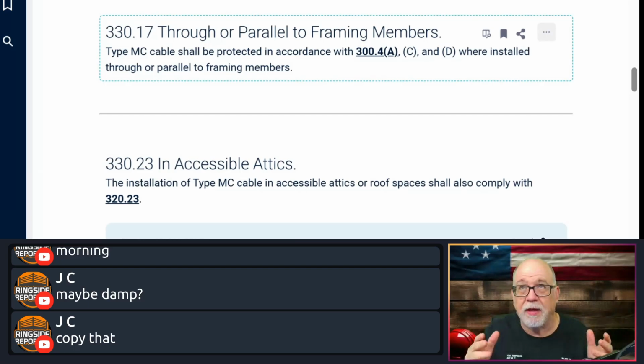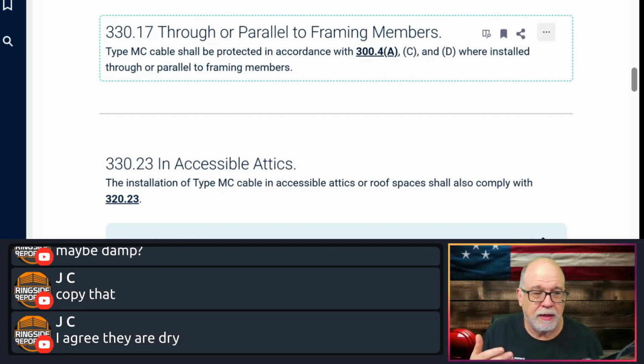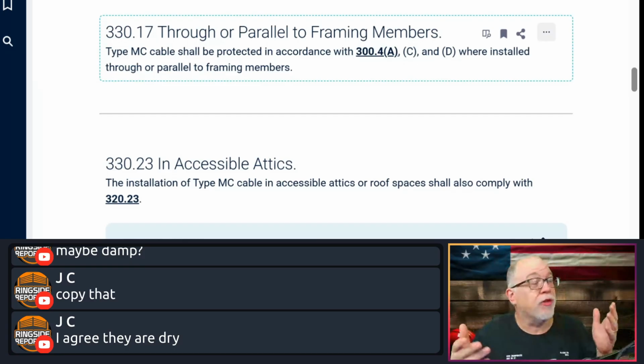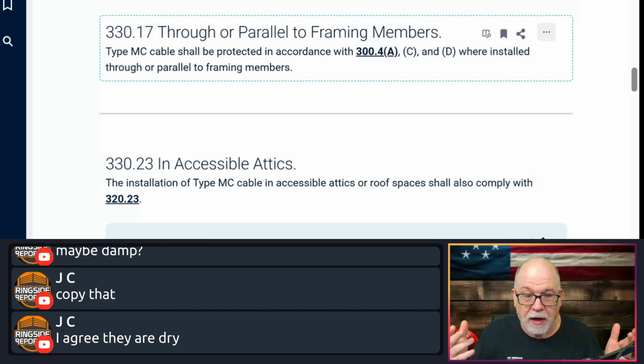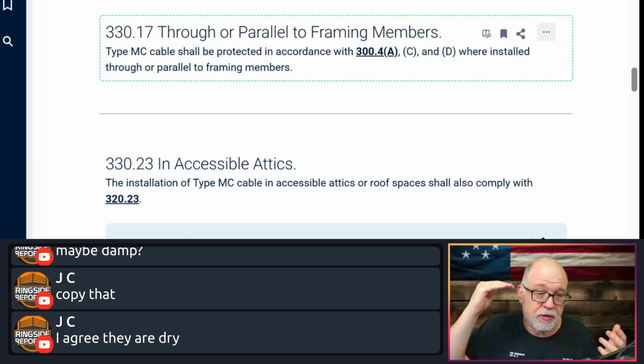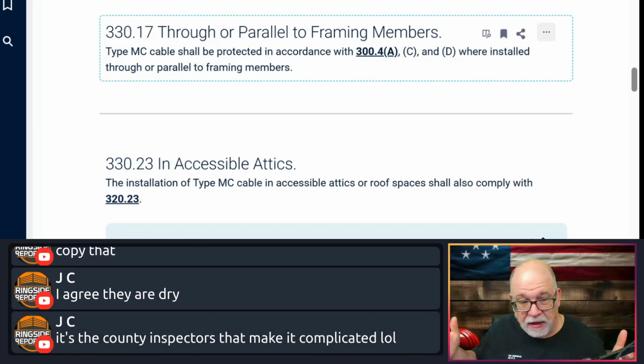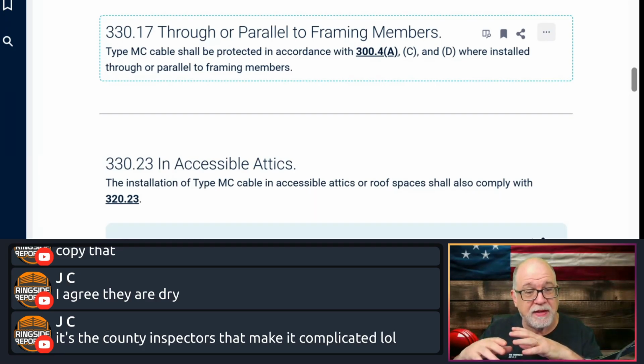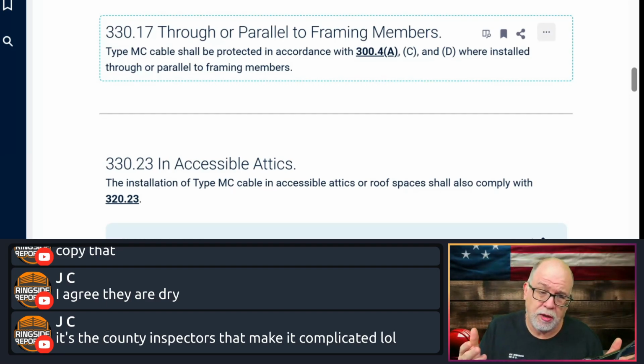Right? Don't. If you get underneath the floor, you'll be able to dictate the environment, or maybe your jurisdiction has other rules as an inspector. Okay. At the end of the day, look around. Look at the other building material that's there. Are they rated for damp or wet location? Probably not. So I'm in a dry location, especially if I'm up in the joists. If you're going to run below it and the dirt looks fine, doesn't look wet, how has it become a damp or wet location? No different than on your porch. Just because you have a porch, does that mean it's damp? Just because I'm in a bathroom, does that make it a damp or wet location because I could have steam in the room? No, it's still a dry location, except for the areas that are designated within the tub or shower spaces. Now, you get what I'm saying? Under a sink. I have people all the time tell me, well, under the sink in a kitchen is a wet location because it has water lines under there.